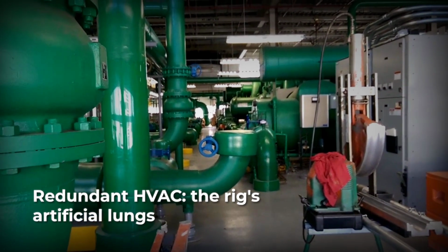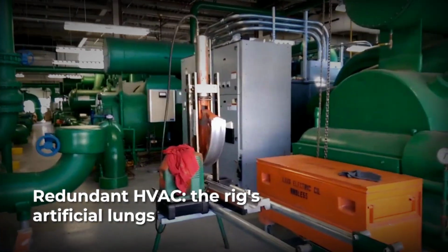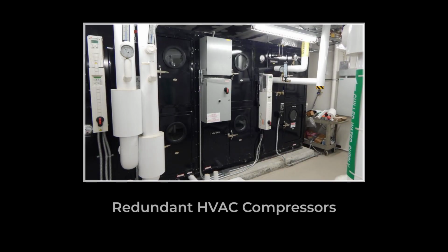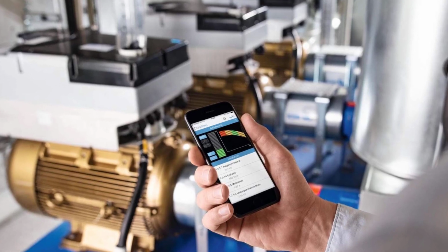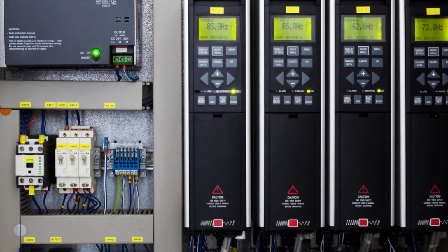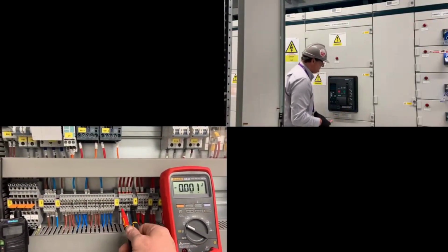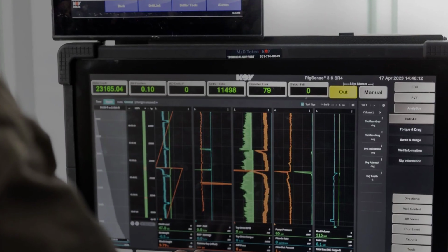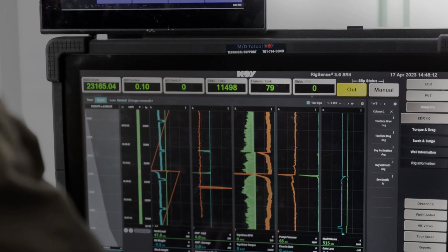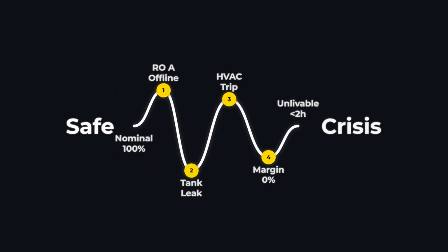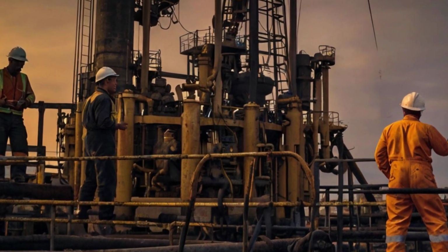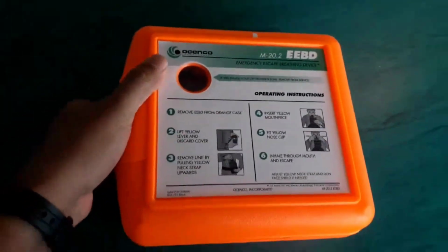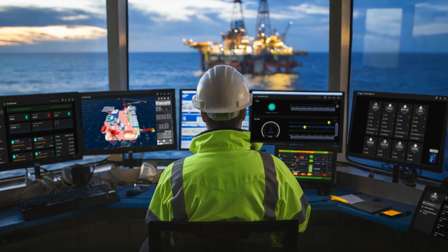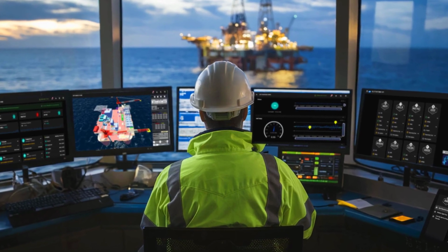Life support extends beyond water. The HVAC system, heating, ventilation, and air conditioning, is built with redundant compressors and independent power feeds. If a compressor fails, its twin takes over. Each unit is paired with a variable frequency drive, so a single electrical fault cannot bring down the entire system. Air quality sensors and positive pressure controls maintain breathable air even during a fire or gas event. Without these overlapping safeguards, a simple equipment fault could cascade into an unlivable environment within hours. The system is designed to buy time, not just comfort. Every minute of buffer, every backup, is a margin against the unpredictable.